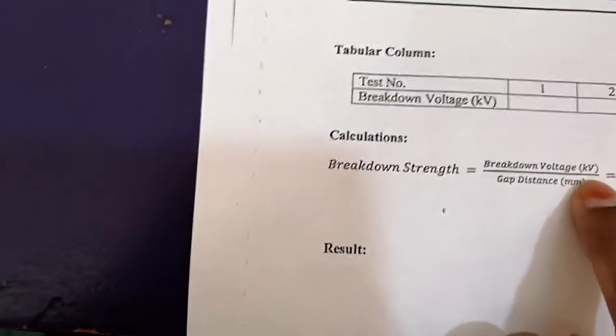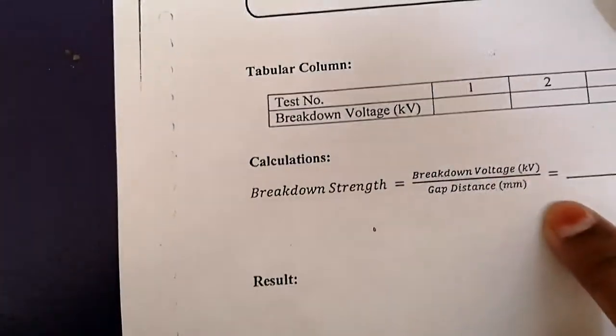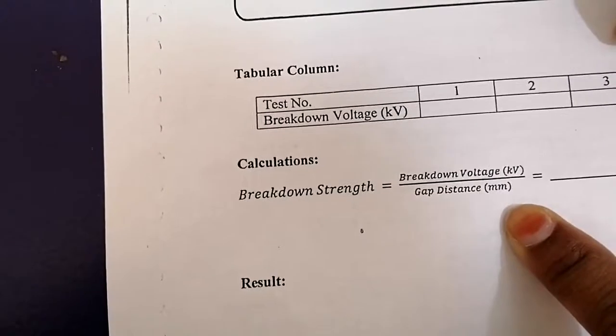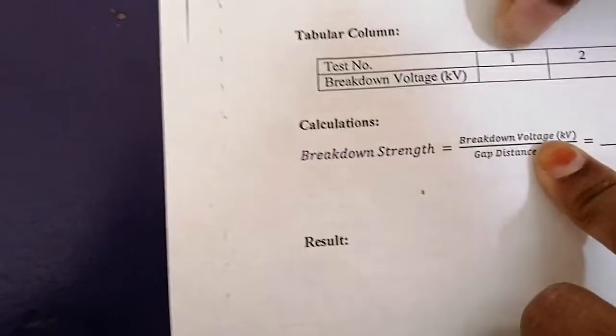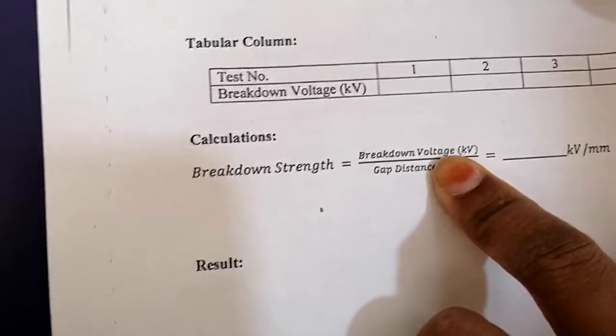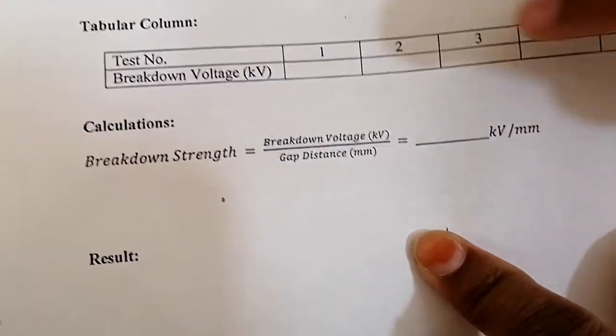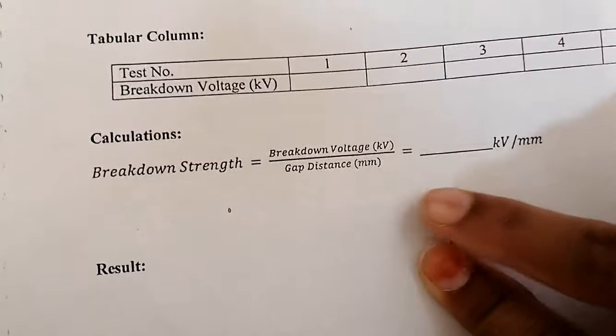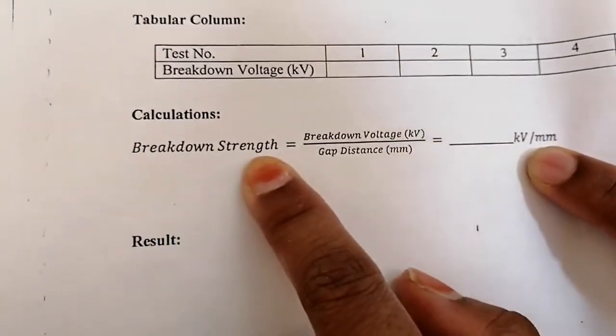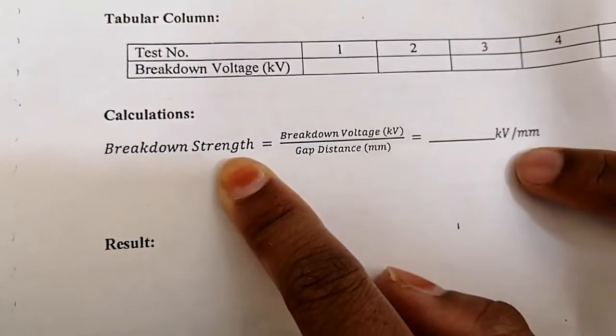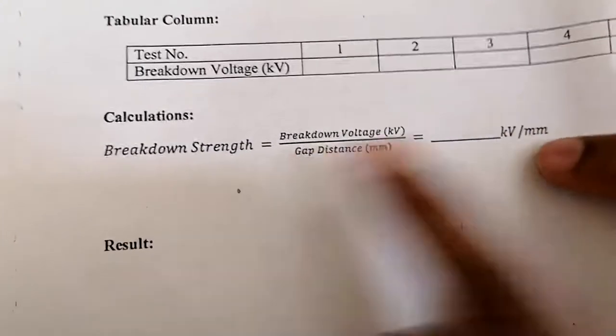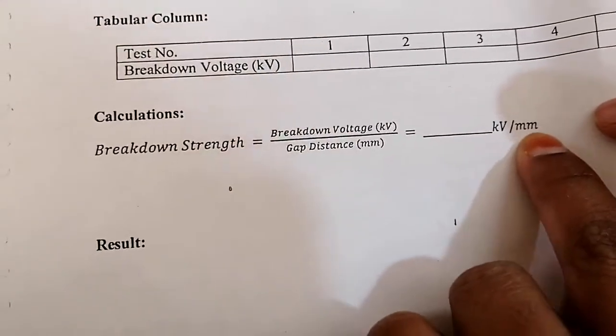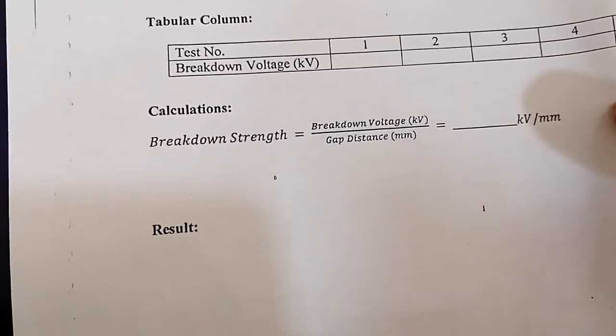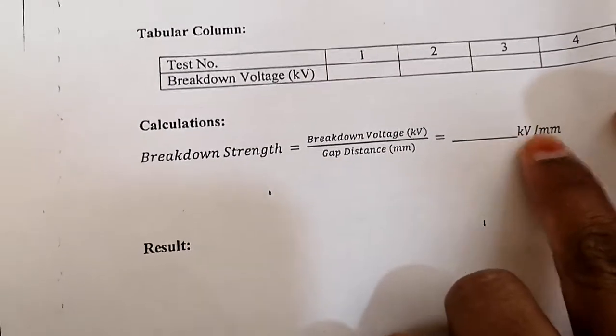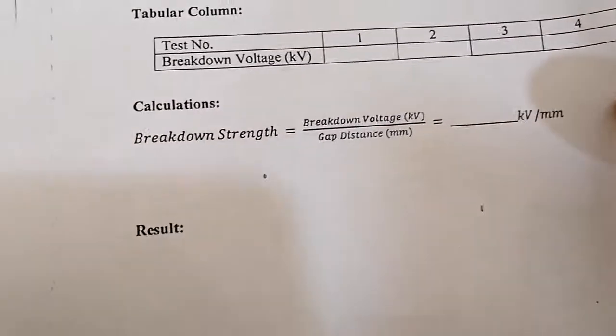Then you have to do the calculation, that is, breakdown voltage divided by gap distance. The gap distance we already know. The breakdown voltage is the mean value of all these trials. The mean value of all the trial voltages divided by the gap distance gives you the breakdown strength. For example, if you get 13 or 14 kilovolt per mm, that means the transformer oil can withstand 14 kilovolt per mm.